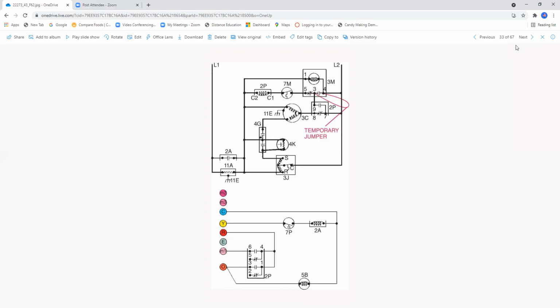Because this is a high voltage circuit, this exercise should not be performed unless the technician is very experienced. So what we're doing here is we're testing the defrost portion of this heat pump by manually overriding the timer with this jumper. Needless to say, extreme care needs to be taken when you are bypassing with a jumper wire so that you can initiate the defrost. Typically on the modern defrost boards, it's on the low voltage side now, but there was a time when you had to do it on the high voltage side.